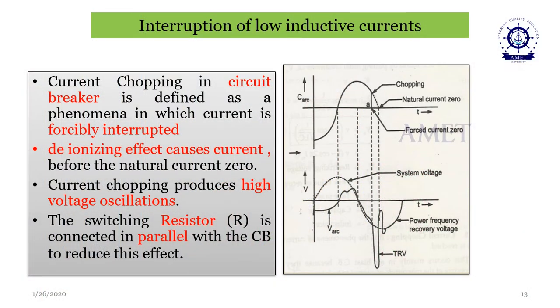When we do like that, there is a deionizing effect of the circuit breaker, which will make the current settle down before the natural current zero occurs. See in the picture, the natural current zero is clearly marked, and this is due to current chopping. What happens is you are forcing the current to become zero. So automatically there is a sudden increase in the system voltage in the second diagram. In the first diagram, the arcing current, the low inductive current, settles earlier than the natural current zero. During such a period, you can observe there is a generation of overvoltage in the system.